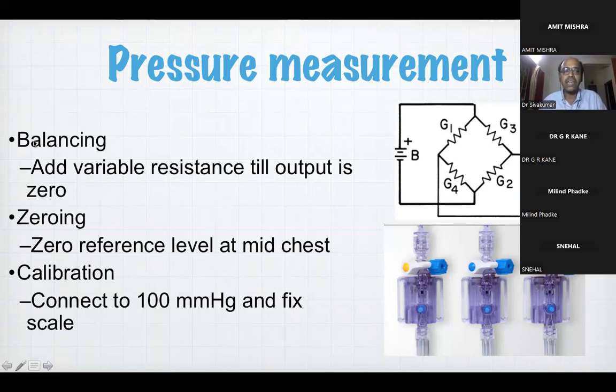So now comes the 3 numbers that we need to understand. What is called balancing? Whenever the fluid filled transducer is not connected to anything at all, the diaphragm is in the neutral position, and G1, G2, G3, G4 are in an unaltered state. The output that comes out should come as 0 in the transducer. So balancing means when you are switching on the transducer, if your value is coming as -2 or +2, that means the machine has to be balanced. So the technician just presses a button and immediately it goes into the balancing mode. And when it goes into balancing mode, the machine automatically adds some resistance to either G1, G2, G3, or G4 and makes the final output as 0.